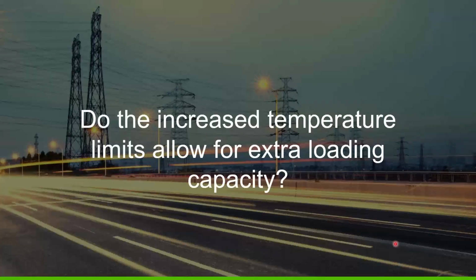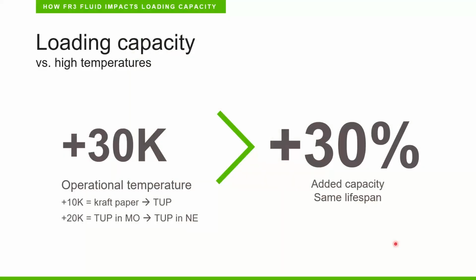Yes, so we learned that it is beneficial for the lifetime of the paper. But of course, then we can say that maybe the increased temperature limits allow us extra loading capacity. Is that possible, Roberto? Yeah, absolutely. From the design point of view, there is a rule of thumb that says that for each degree of increase in the average winding temperature rise, you get an increase of 1% in the load of the transformer, the capacity of the transformer.